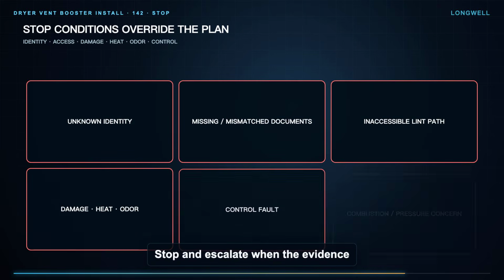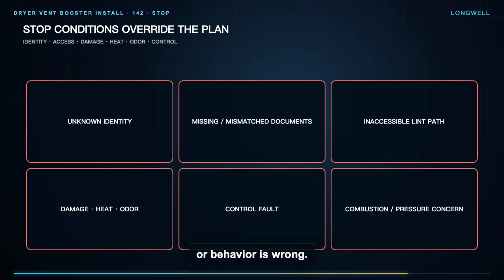Stop and escalate when the evidence or behavior is wrong. Stop for an unidentified fan, mismatched documents, missing label, prohibited location, inaccessible lint path, damaged duct, uncertain electrical method, unusual heat or odor, repeated control fault, visible lint leakage, or any combustion and pressure concern. Do not defeat a safety device or keep operating to see if it clears. Isolate the equipment as required and involve the manufacturer, a qualified installer, and the local authority where appropriate.